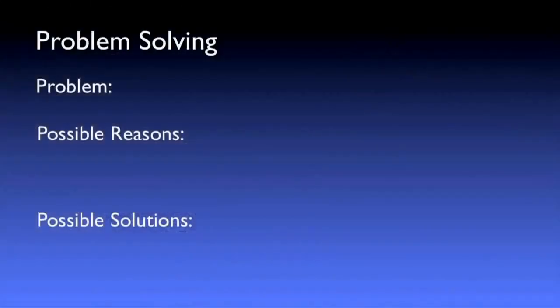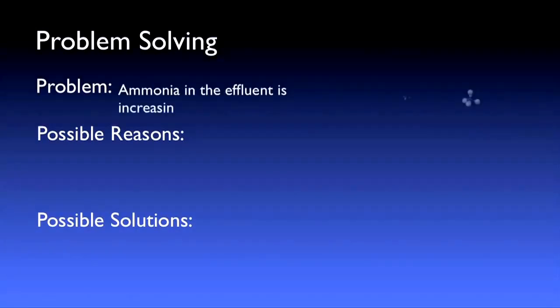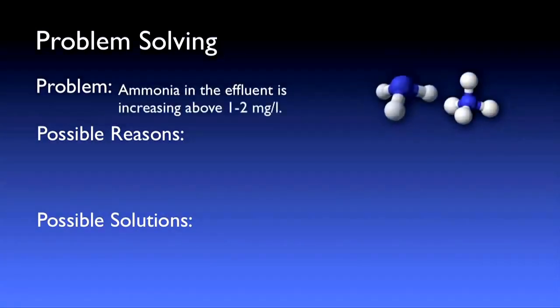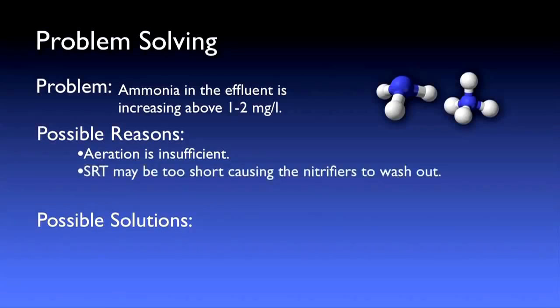Now let's take a look at some real-life operational scenarios. During routine operational sampling, you notice that the ammonia in the effluent is beginning to rise above 1–2 mg/L. We know that nitrification is an oxygen-hungry process, so perhaps the aeration is insufficient. We also know that nitrifiers grow more slowly, so perhaps the SRT is too short due to a temperature influence.